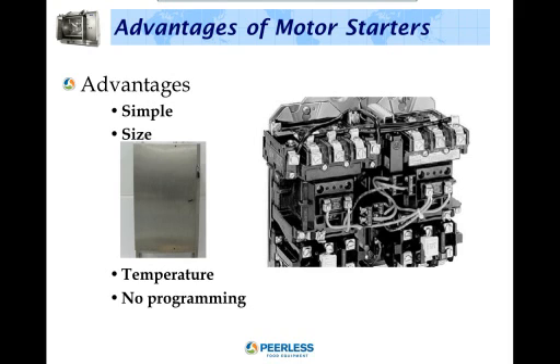Advantages of a motor starter. They're simple. There's no complicated electronic circuits. Easy to replace broken parts. The size. The control enclosure will be smaller than a system running on a VFD of equal horsepower. In some bakeries, space can be hard to come by. Temperature. This system is simple and does not include any transistors that may be expected to generate heat. Cooling will not be required for the system to remain operational, and no software to program will be needed.